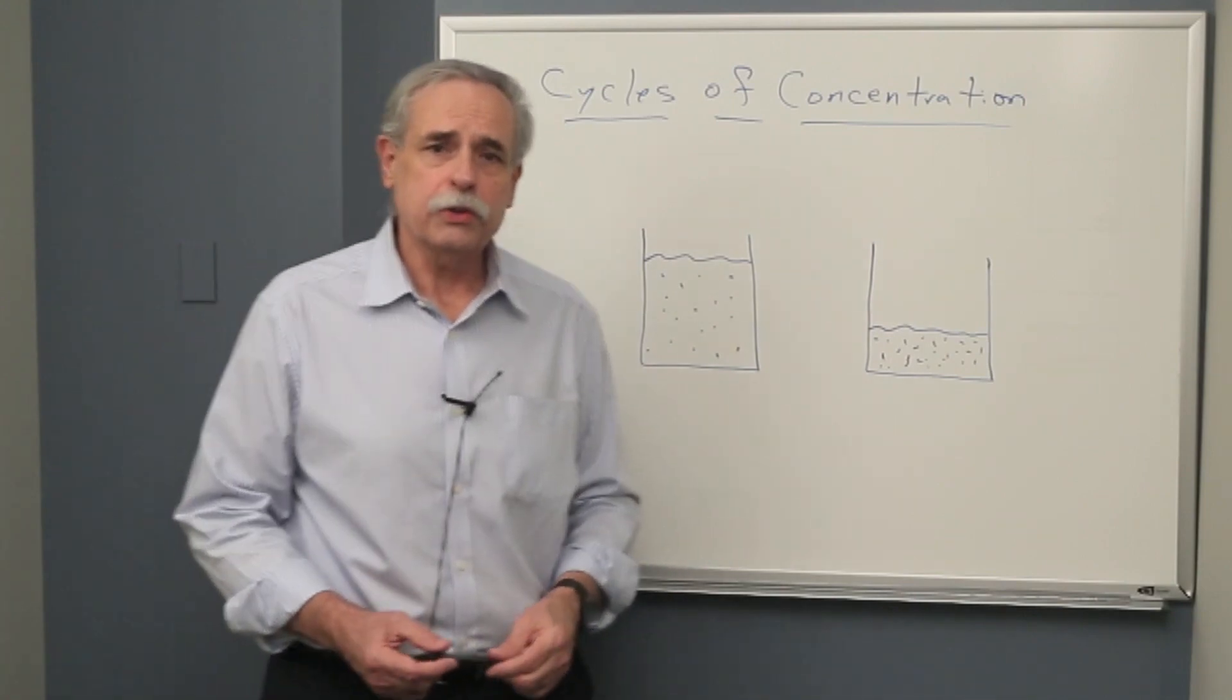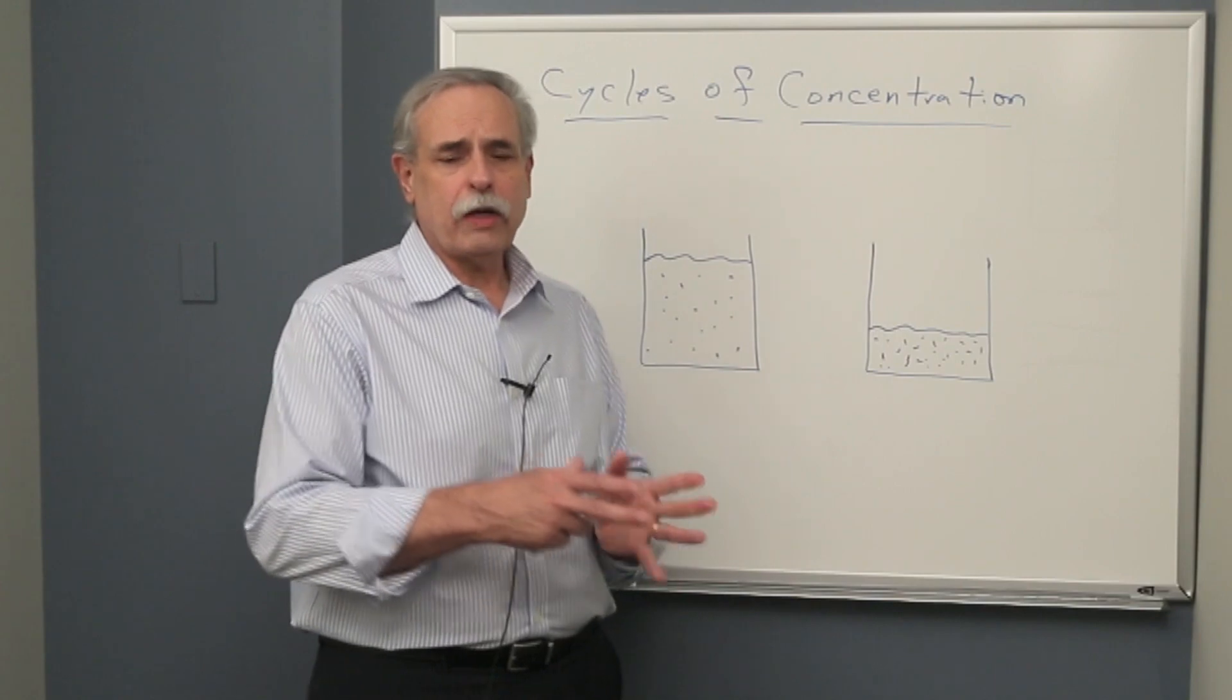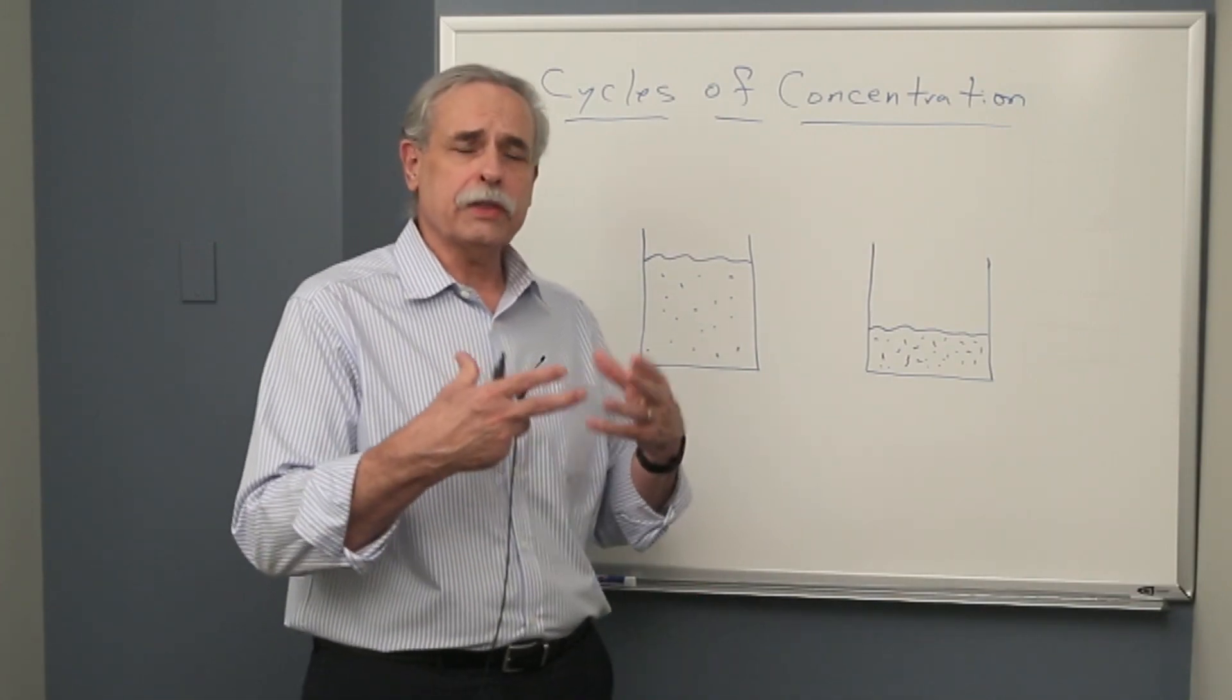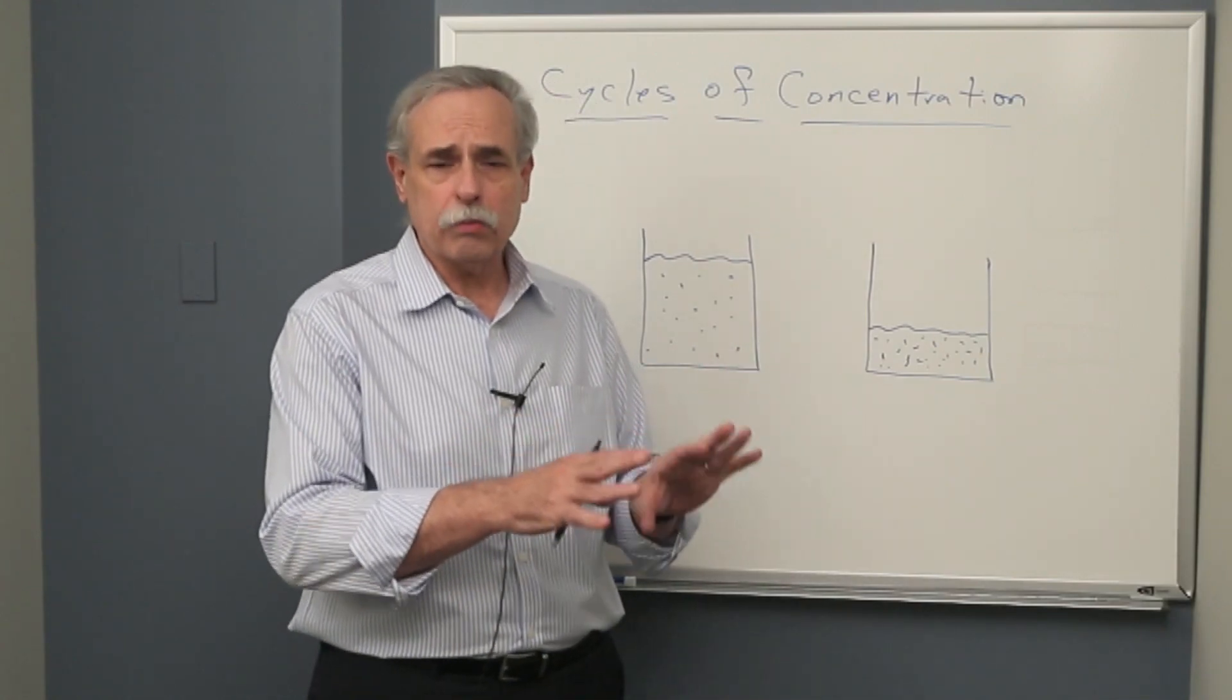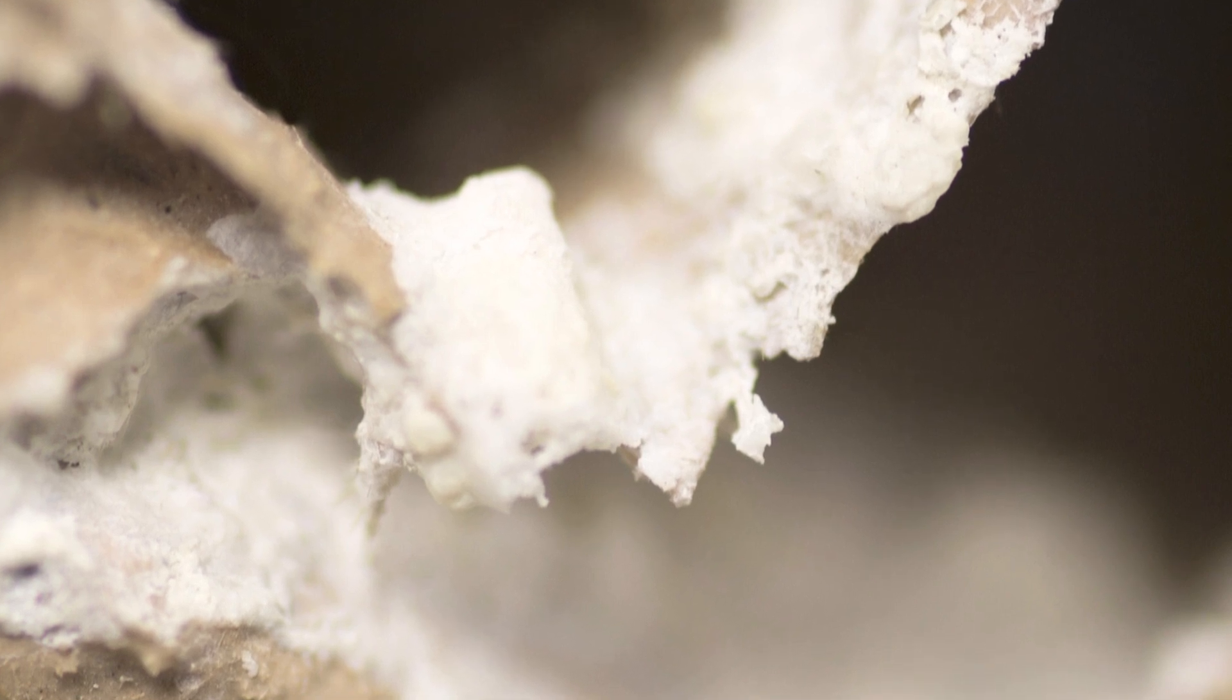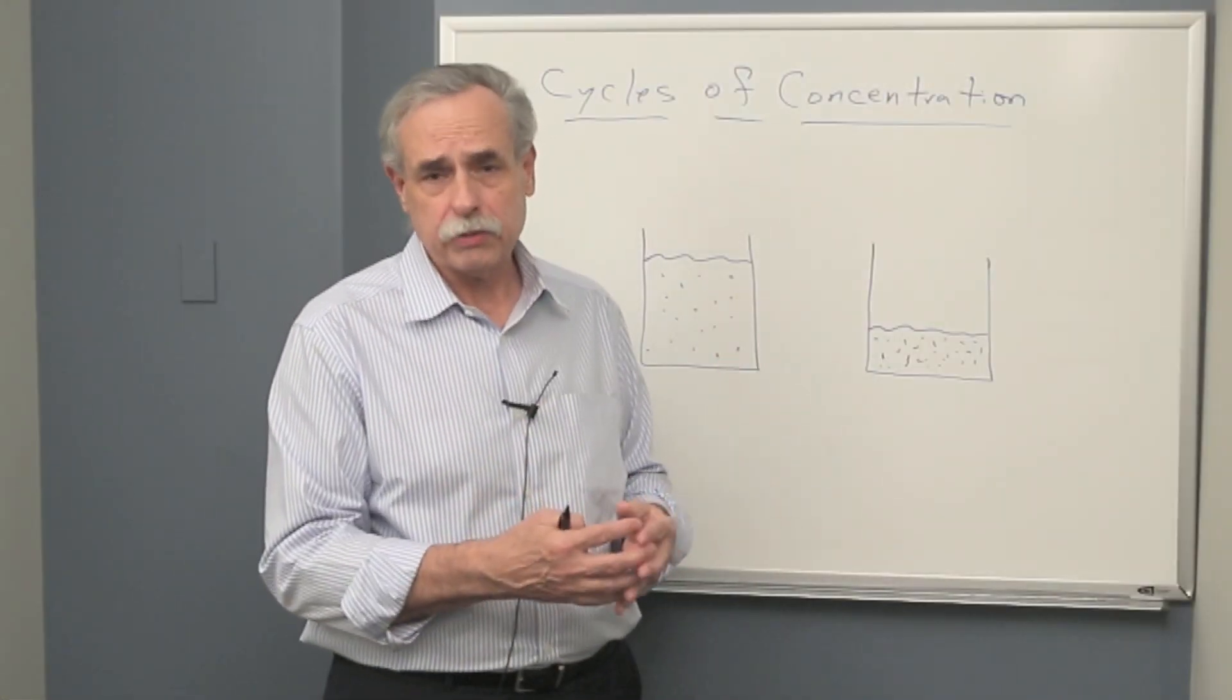So why is that important to a wetted media system? First, let's say you have a certain quality of water coming to the system and your concentration cycles is too high. What could happen is that over time you form excess scale buildup, potentially affecting air flow through the media, and even potentially over enough time affecting the structural integrity of the media.